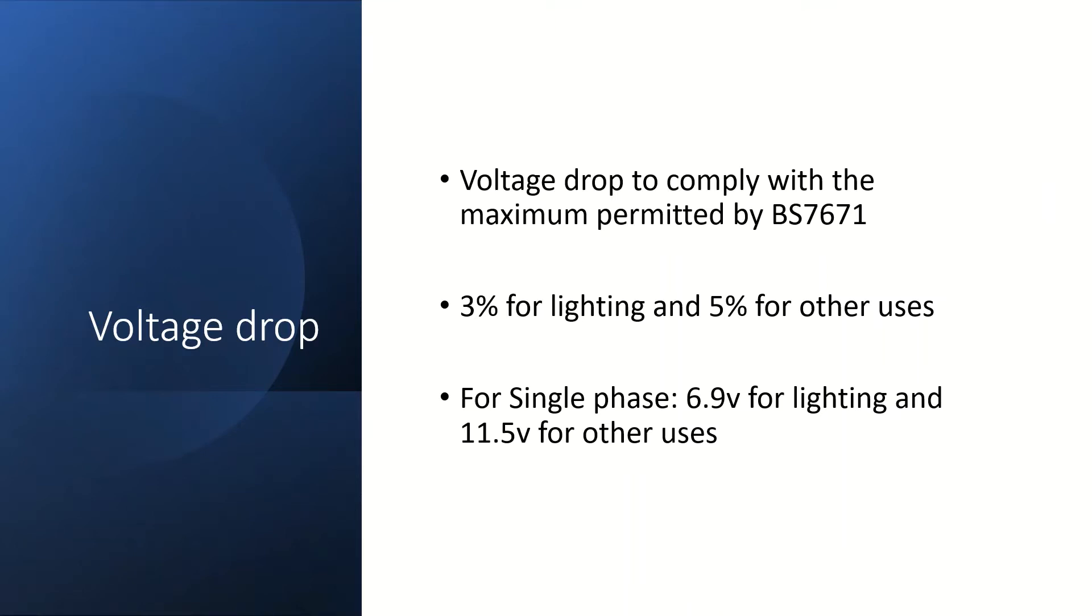The length of the final circuits affects the volt drop and it is necessary to ensure that the volt drop doesn't exceed the maximum permitted by BS7671 which is 3% for lighting and 5% for other uses.